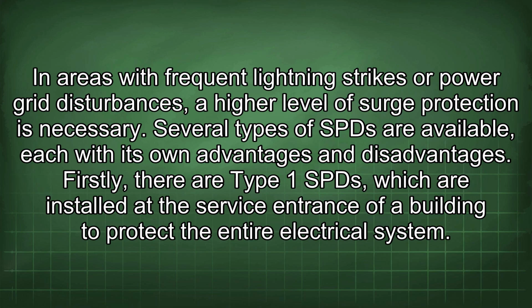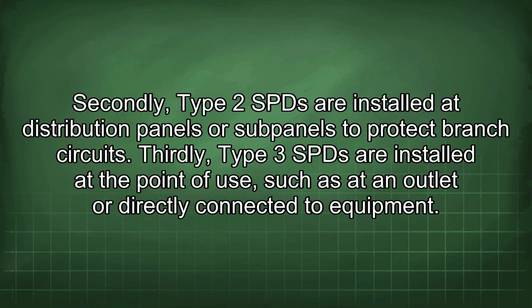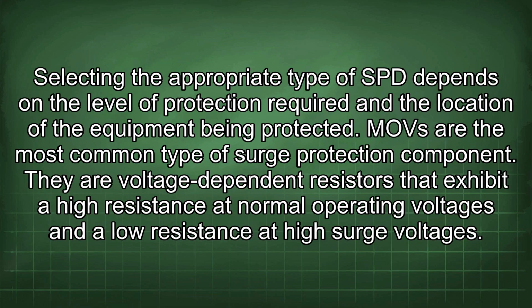Several types of SPD are available, each with its own advantages and disadvantages. Firstly, there are Type 1 SPDs, which are installed at the service entrance of a building to protect the entire electrical system. Secondly, Type 2 SPDs are installed at distribution panels or subpanels to protect branch circuits. Thirdly, Type 3 SPDs are installed at the point of use, such as at an outlet or directly connected to equipment. Selecting the appropriate type of SPD depends on the level of protection required and the location of the equipment being protected.